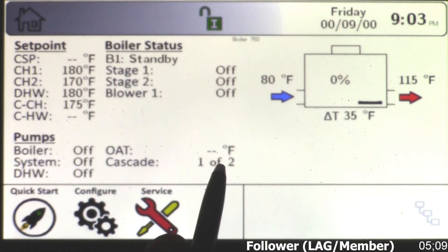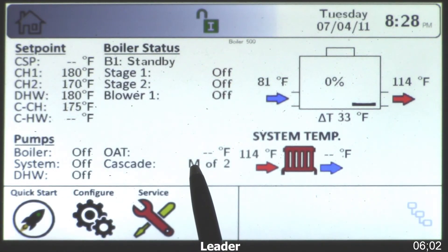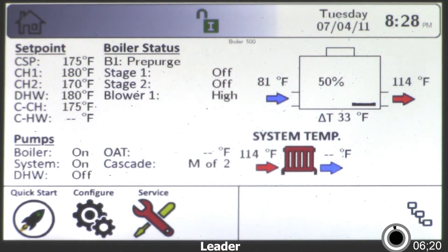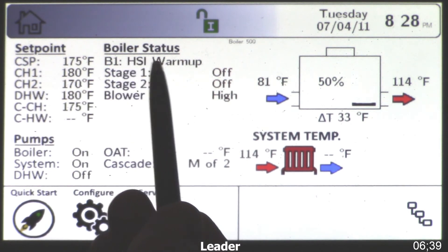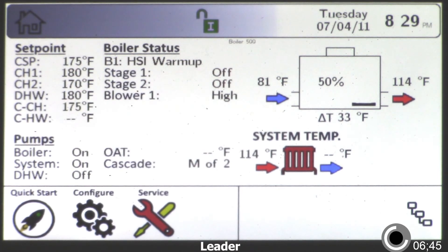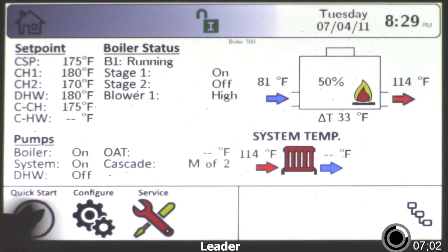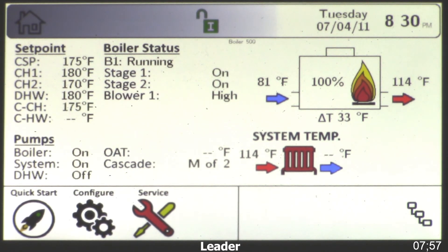It's now reading one of two boilers. Back at the lead boiler, it's reading M for master of two. I'm going to go ahead and give this boiler a call for heat. Now we're pre-purging, then into HSI warm-up — that's your hot surface ignition warm-up. This is only a two-stage boiler with one blower and one igniter. Now we're into ignition and now we're running — we were at 50 percent and modulating to 100 percent. Be patient.